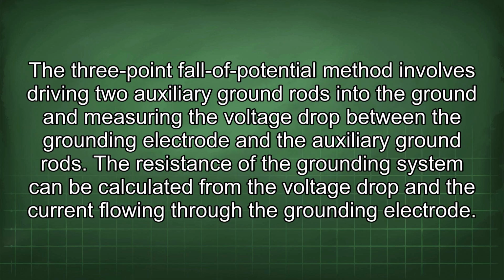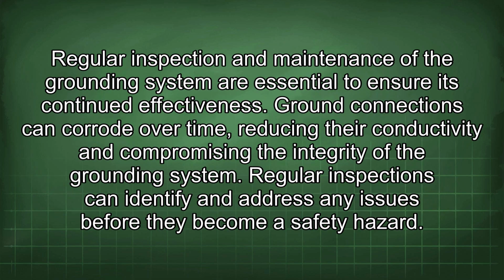The 3-point fall of potential method involves driving 2 auxiliary ground rods into the ground and measuring the voltage drop between the grounding electrode and the auxiliary ground rods. The resistance of the grounding system can be calculated from the voltage drop and the current flowing through the grounding electrode. Regular inspection and maintenance of the grounding system are essential to ensure its continued effectiveness. Ground connections can corrode over time, reducing their conductivity and compromising the integrity of the grounding system. Regular inspections can identify and address any issues before they become a safety hazard.